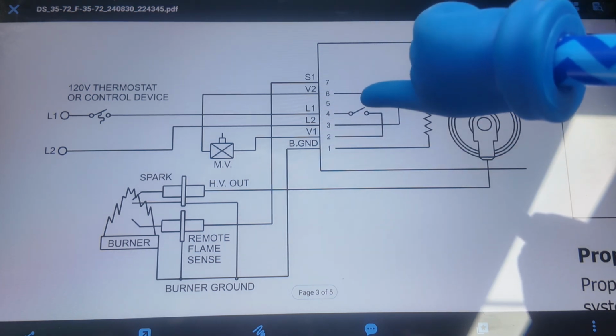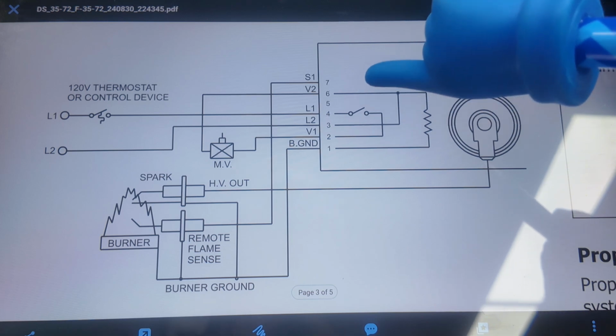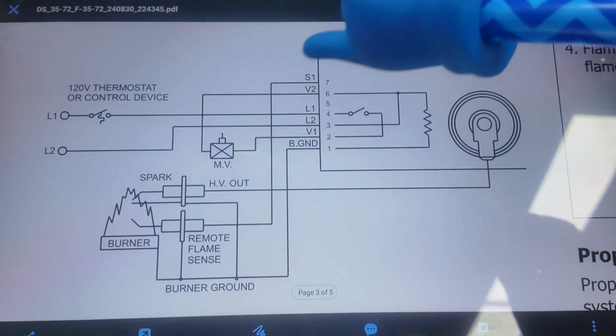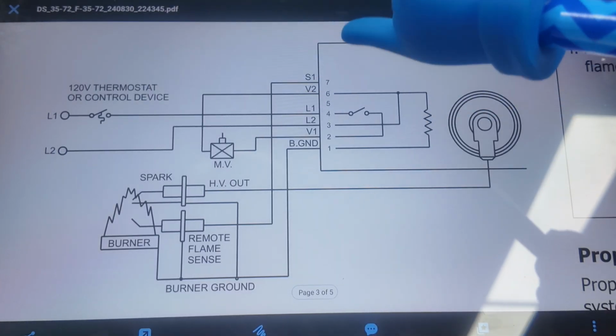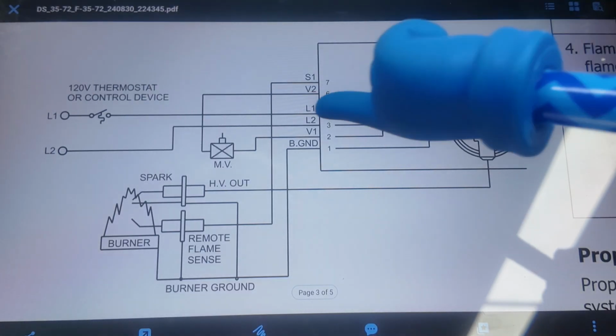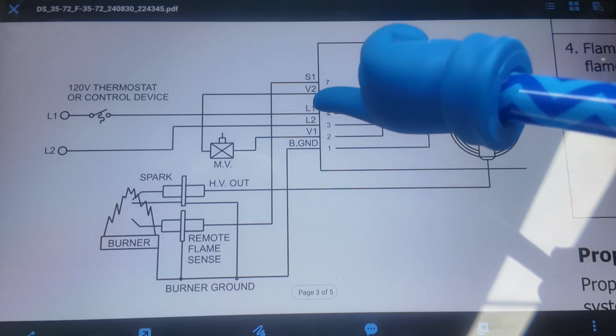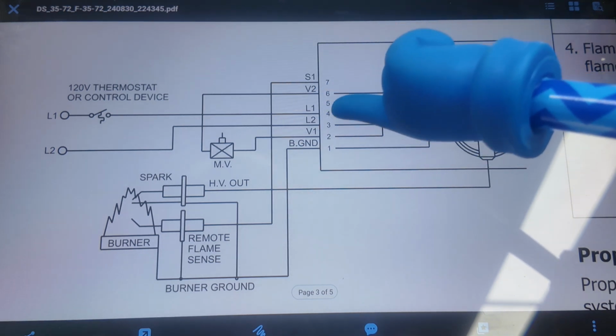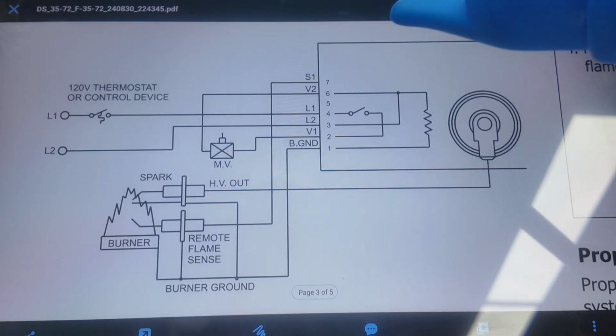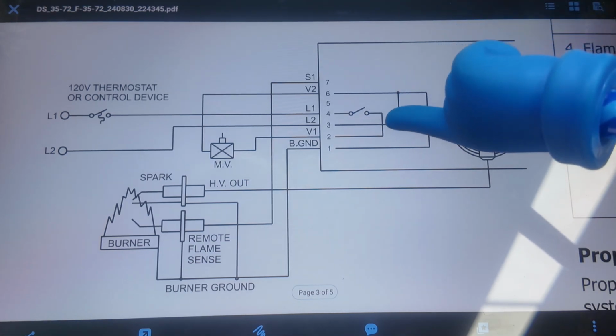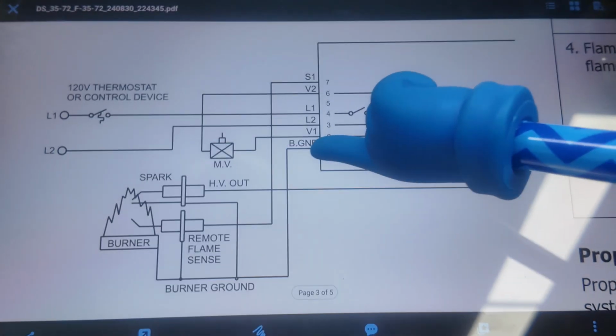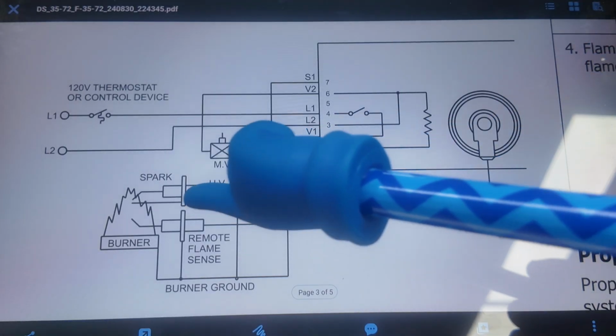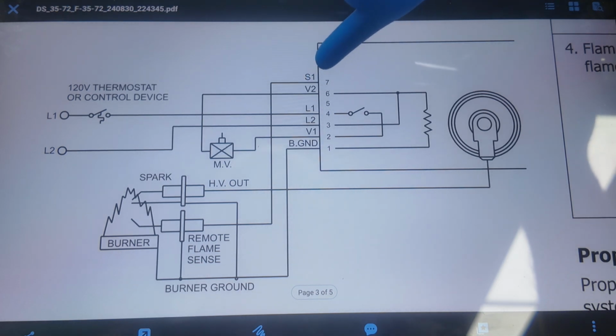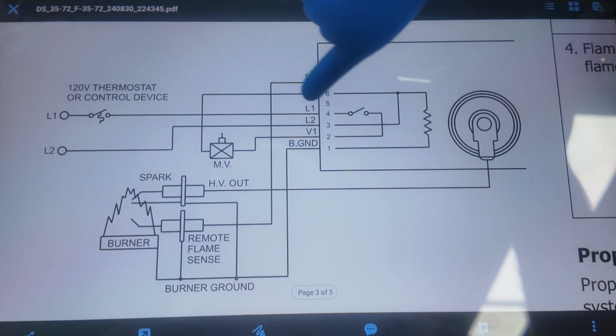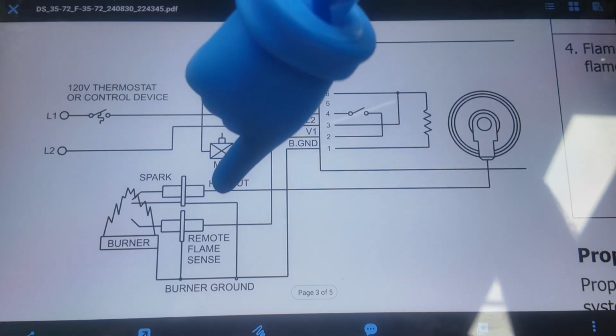Because this will not close. It'll say we have a problem with our flame sensing. So if we disconnect the wire from S1, and we put 120 volts to L1 and L2 after the ignition time, this switch should close and we should get voltage out, V1, to power the main gas valve and spark. If we have S1 disconnected and we put power here and we do not get power out, there is a problem.